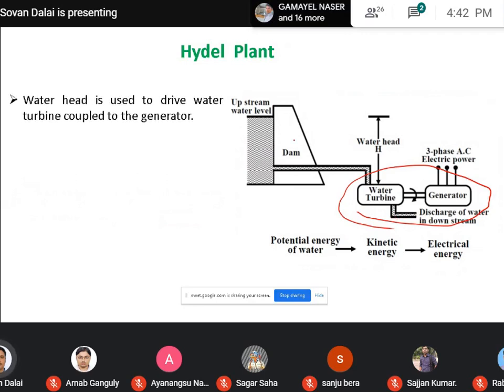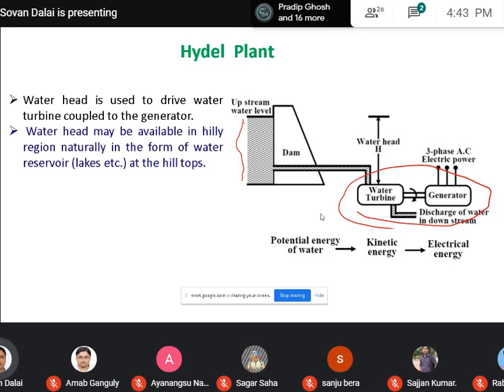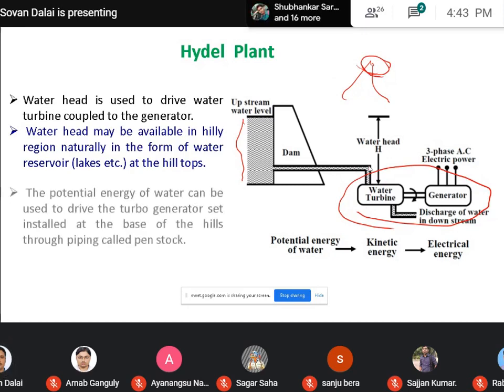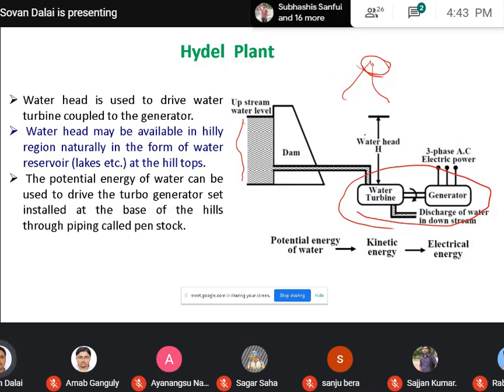So what is the principle here? Water head. The water head can be natural or artificial. The water head is used to drive the water turbine that is coupled to the generator. Generally, a water head may be available in hilly regions, naturally in the form of a water reservoir like a lake at the hilltop. If a natural lake is there on a hilltop, that lake water can be used as the water head for running the water turbine. But in most cases it is not always available, so we can build an artificial water head in a certain area.